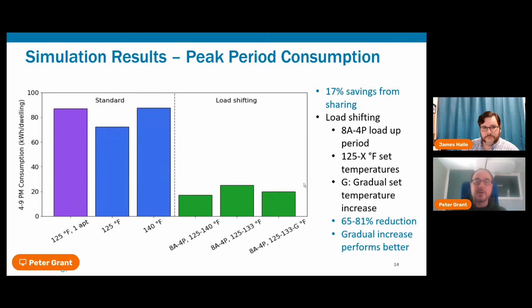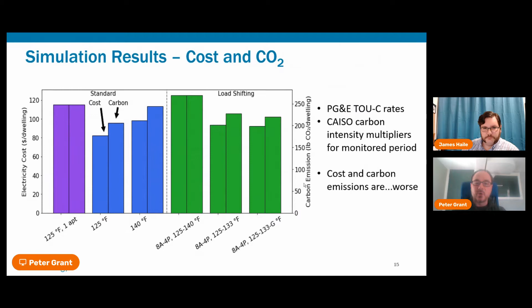But when we look at cost and CO2, the results aren't quite as straightforward. We still see a big improvement switching from individual heat pump water heaters to the shared configuration. But when we start implementing load shifting in the shared configuration, we actually see cost and carbon dioxide emissions increase. So what happened? Well, the problem is that these units, since they're shared between 4 apartments, already have high loading. And the heat pump is already struggling to keep up with the load. And then when we start increasing the set temperature, we're also increasing expectations at the same time that they're struggling.